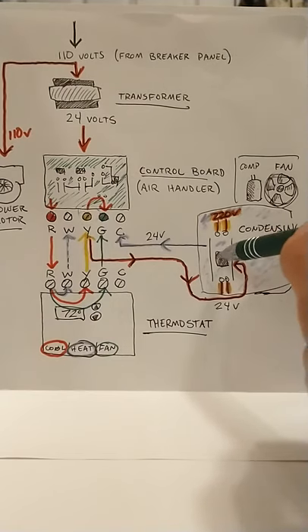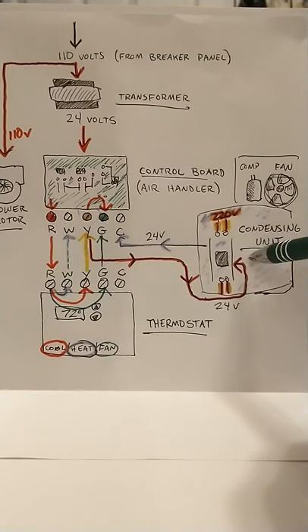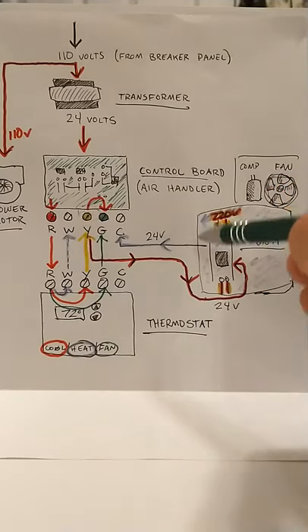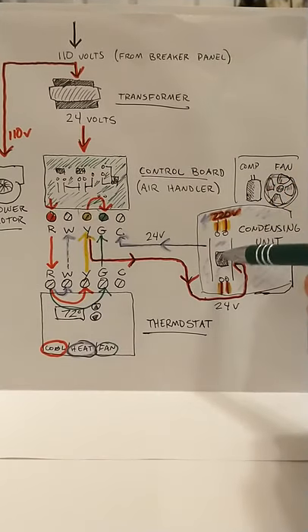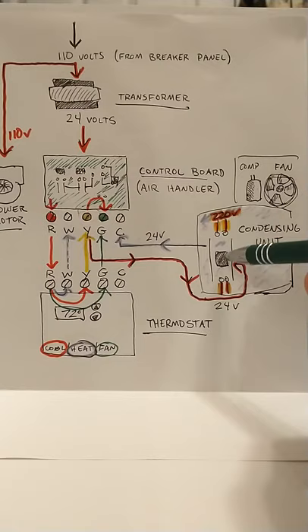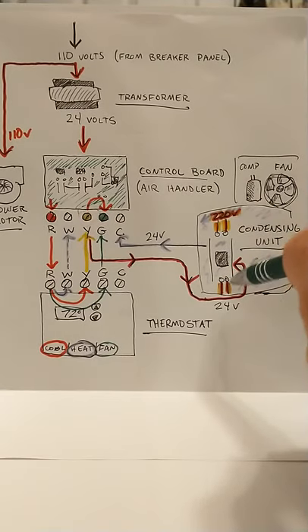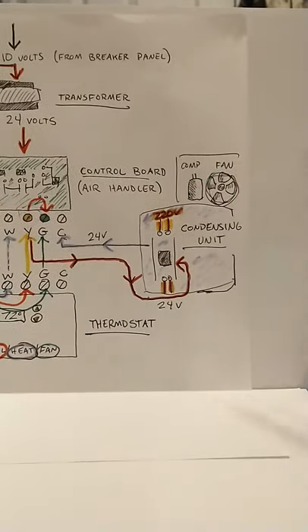It'll go to a contactor. When your 24 volts flows through that contactor, it creates sort of like a magnet that pulls that switch in. When that switch is pulled in, it allows your 220 volts to travel through it, which powers your compressor and your fan. So the whole outdoor unit will actually start up.